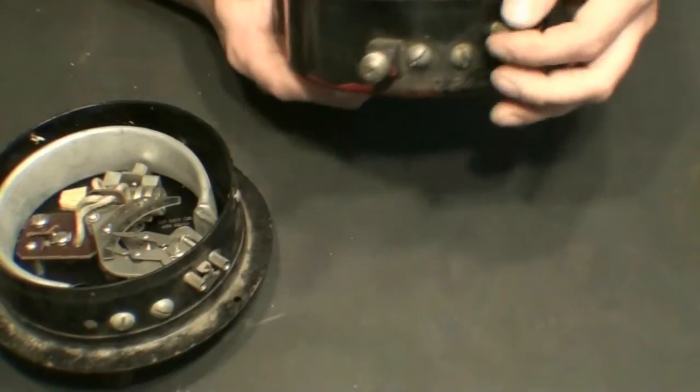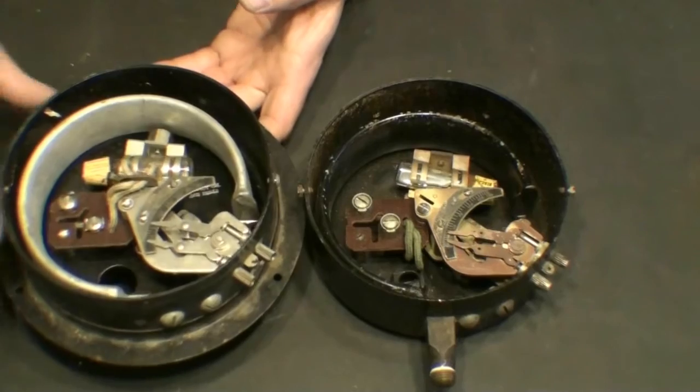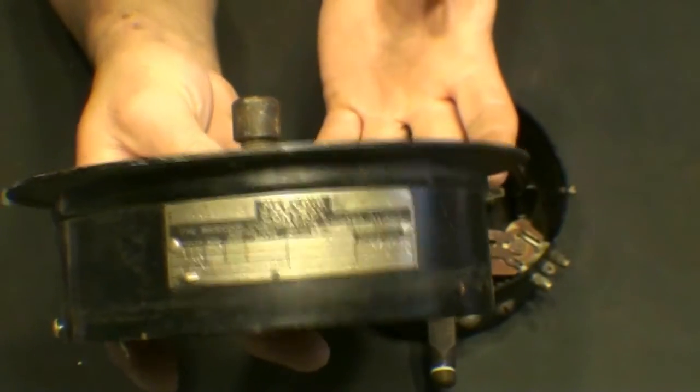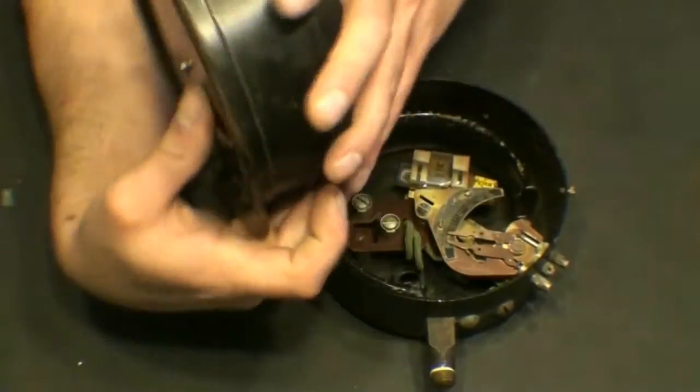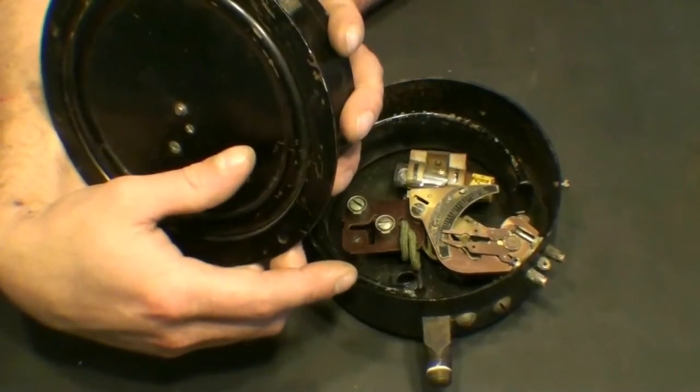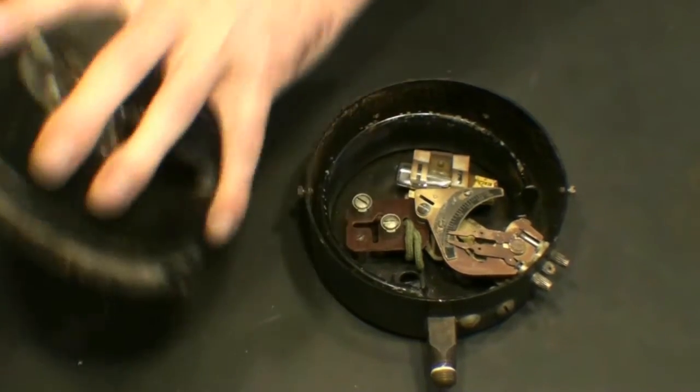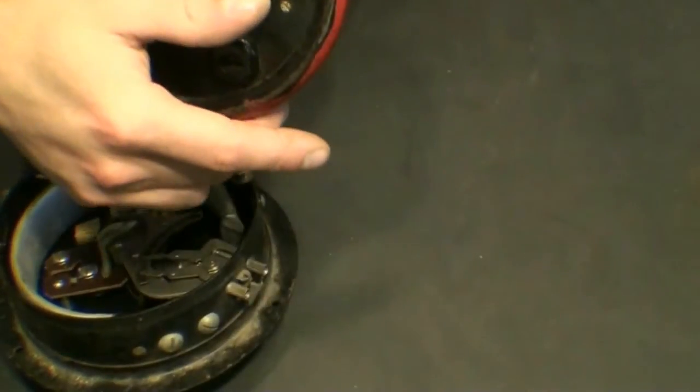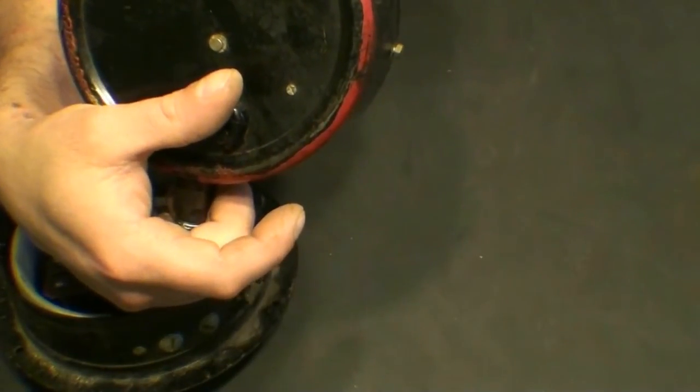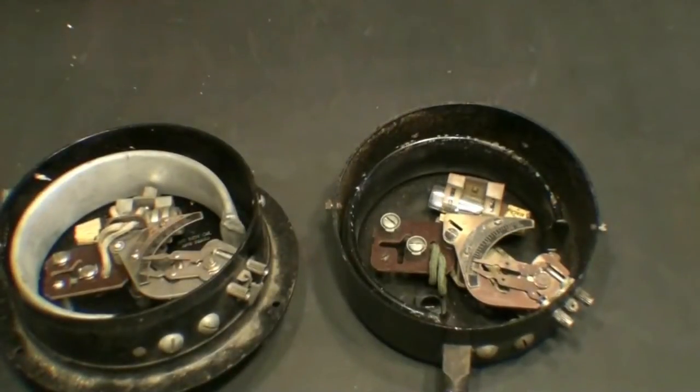But anyway, there we have it, mercury pressure switches. You can see there's the rating tag. It says it is rated 115 volt 10 amp, 230 volt 5 amp, single pole single throw switch, single phase, half horsepower rating, and DC half horsepower.